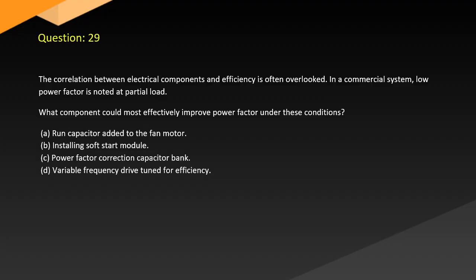Question 29. The correlation between electrical components and efficiency is often overlooked. In a commercial system, low power factor is noted at partial load. What component could most effectively improve power factor under these conditions? A. Run capacitor added to the fan motor. B. Installing a soft start module. C. Power factor correction capacitor bank. D. Variable frequency drive tuned for efficiency.